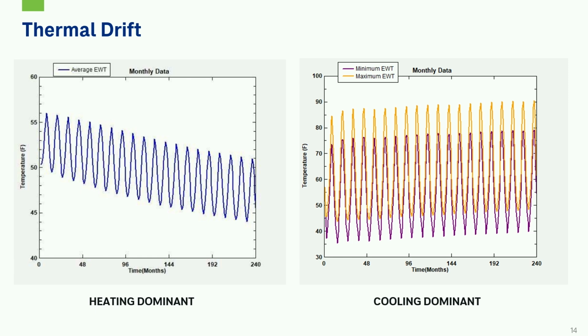Sure. Hi, so do we expect that to flatten, or will it continue to pull? Obviously, ground temp is going to have it flatten, but do we expect that to fail at some point, or is it going to level out? What do we expect for a design? So it won't level out. It will continue to drift. As you add more cooling load in, the ground will continue to get hotter. And then opposite, if you have a heating dominant system, the ground will continue to get colder. We're just looking at a 20-year snapshot right here.